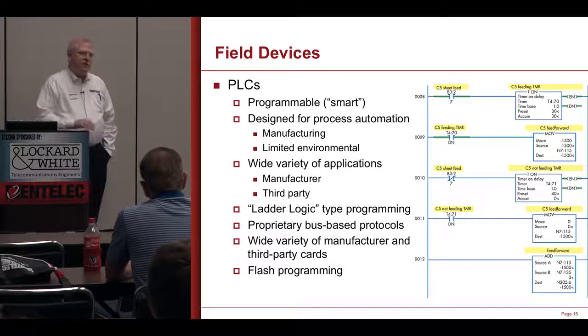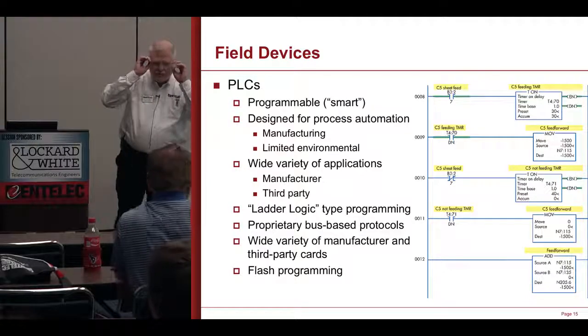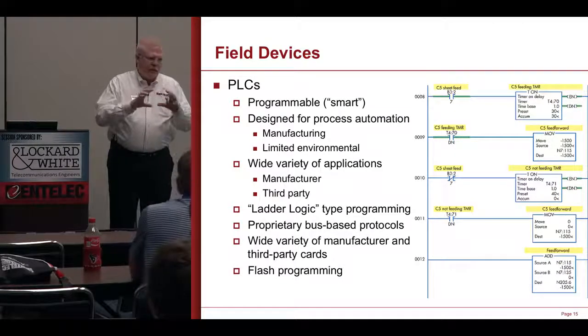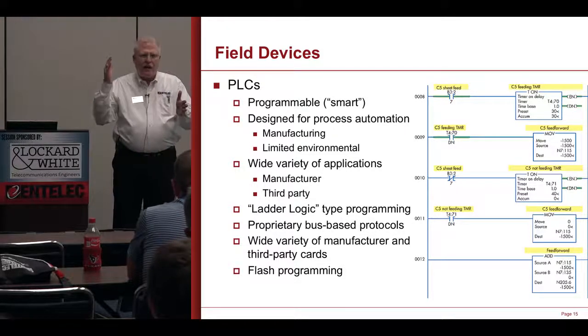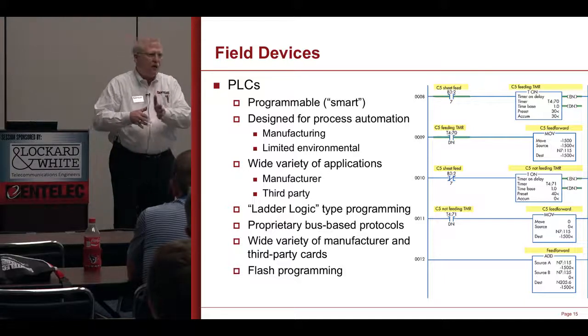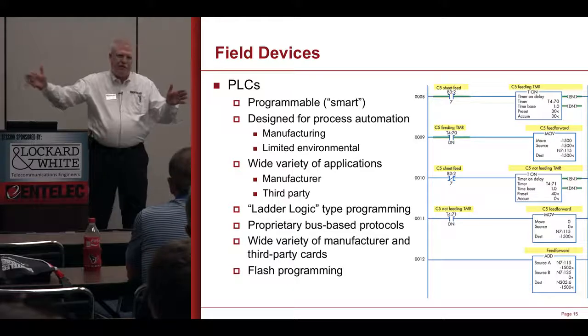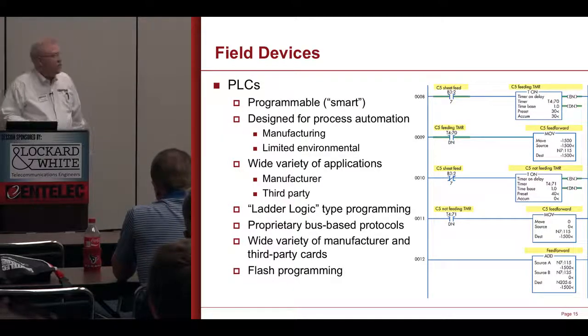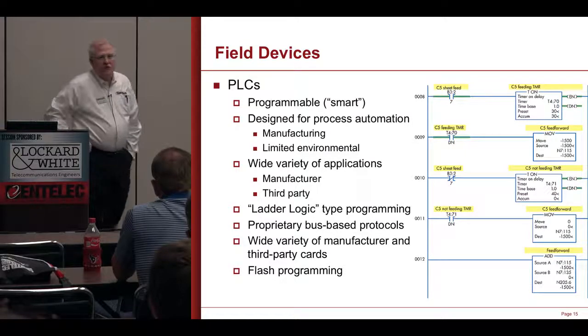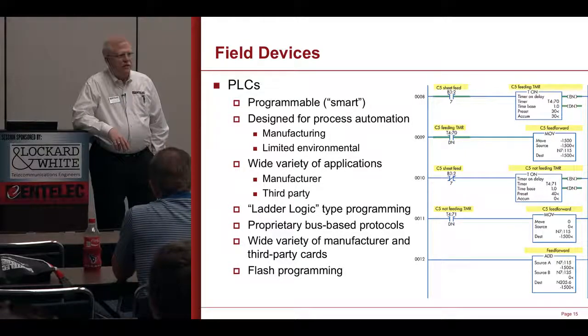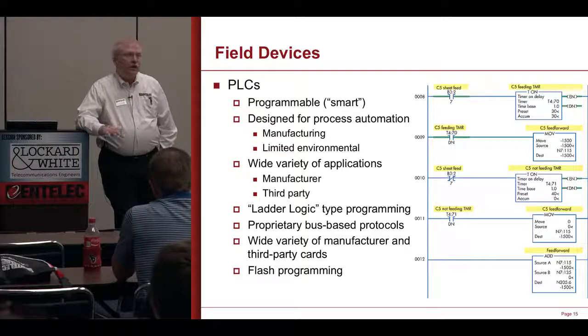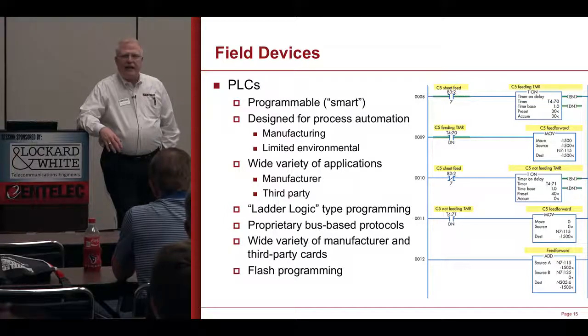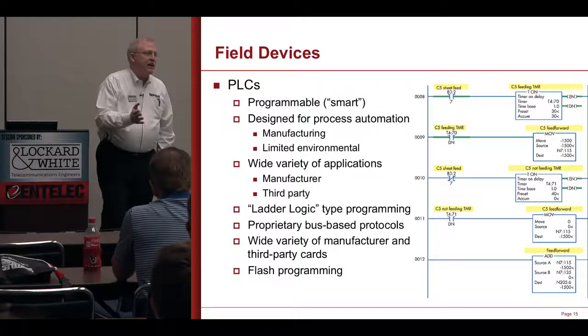There are a lot of manufacturers. With the bigger PLCs — not the micros — I buy a processor, then a comm card, IO cards, and remote IO cards, and plug them all into a chassis, expanding it based on what I need. Some manufacturers make triple redundant PLCs, where the communications, processor, and IO are all redundant threefold. That was developed primarily for the nuclear power industry when they needed absolute surety of maintaining control of the process.